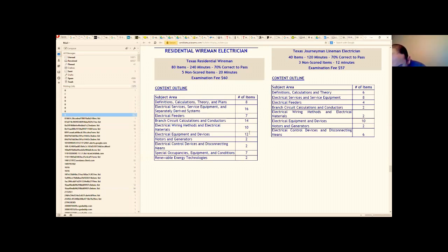What is this table doing? Like telling you what kind of wire you can use? Given the kind of wire you're going to use and the location you put it, it's telling us the ampacity of that wire. And so this is kind of our core steps of sizing the feeder or sizing a branch circuit conductor. This is the wire ampacity table that you start with.